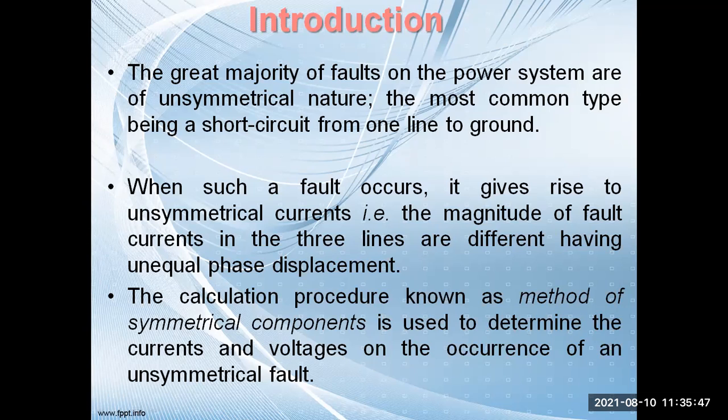That is, the magnitudes of fault current in the three lines are different, having unequal phase displacement. But if it is a symmetrical fault, in that case the phase displacement will be the same. Now, the calculation procedure known as the method of symmetrical components is used to determine the currents and voltages on the occurrence of an unsymmetrical fault.